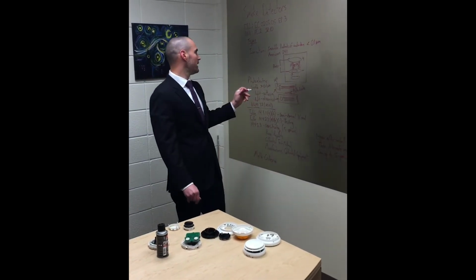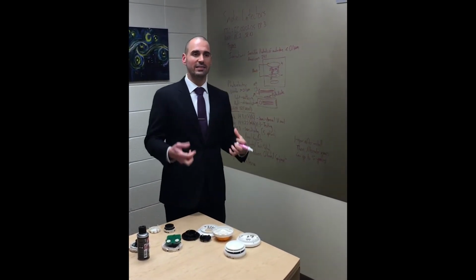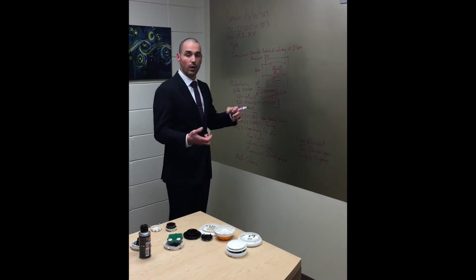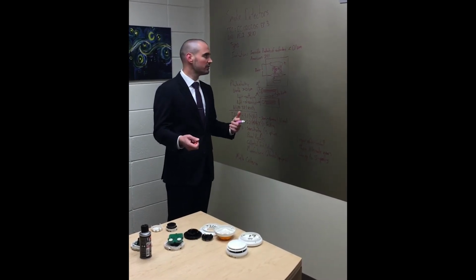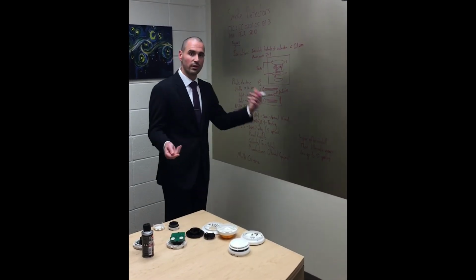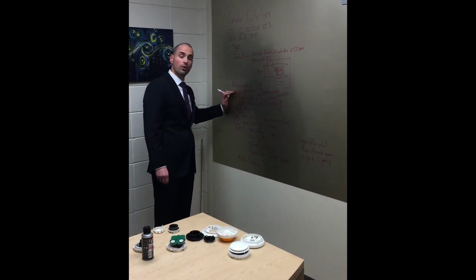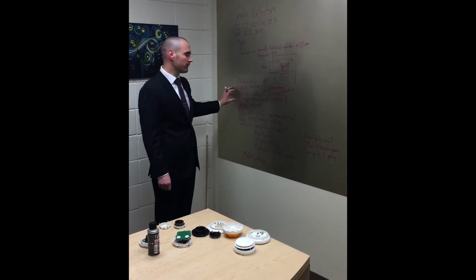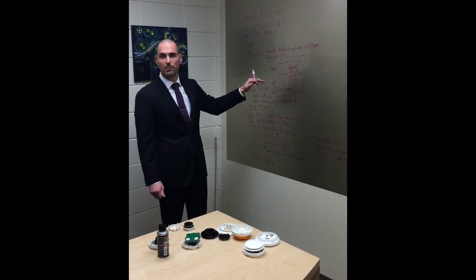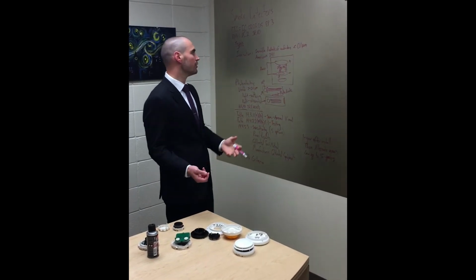I think it's important to note that ionization actually picks up fires more quickly from a fast burning fire. And if you think about that from the perspective of where they're used in houses, a house is a giant combustible product. Lots of combustible interior finishes, versus photoelectrics that can detect slow smoldering fires, which is more common what you would see in healthcare. And that's because we limit combustibility significantly in healthcare, where we use non-combustible and limited combustible construction. So it does matter where these are placed and how they're used as well.